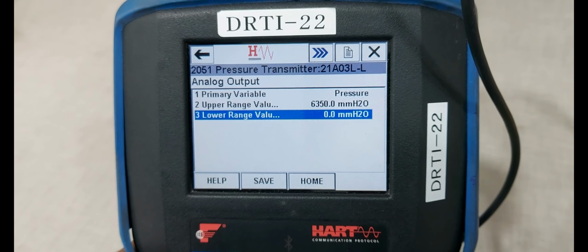Now we remove the pressure from the unit. Now the transmitter is showing the 0 value. Output also showing the 0 value. Okay, then press OK. Okay, low trim is successfully completed. Then press OK. Next we are doing the upper sensor trim.